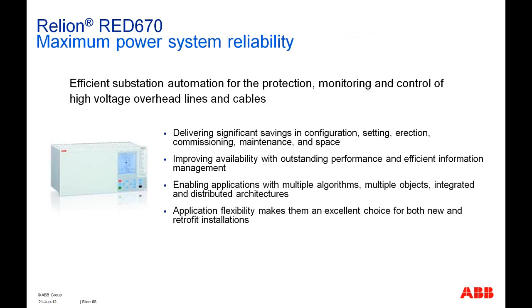Relion is a brand name of ABB protection devices, and RED 670 is the line differential relay. Relion is efficient substation automation for protection, monitoring, and control of high voltage overhead lines and cables, delivering significant savings in configuration, setting, erection, commissioning, maintenance, and space, improving availability with outstanding performance and efficient information management, enabling applications with multiple algorithms, multiple objects, integrated and distributed architectures. Application flexibility makes them an excellent choice for both new as well as retrofit installation.